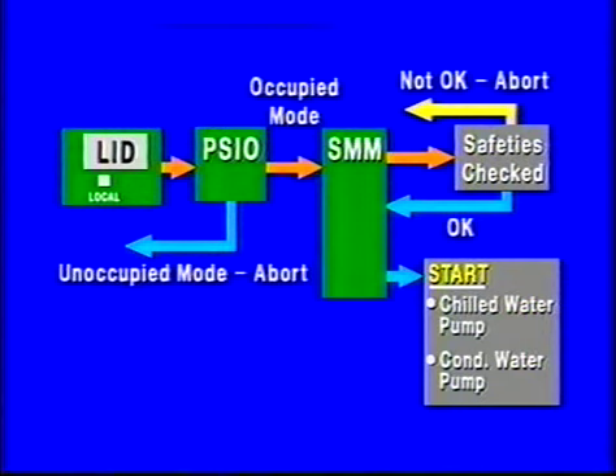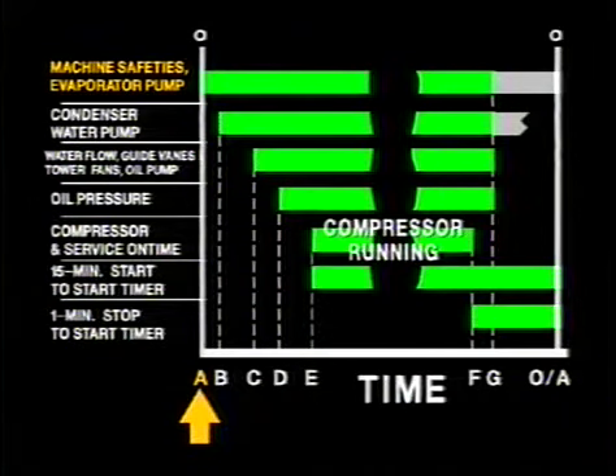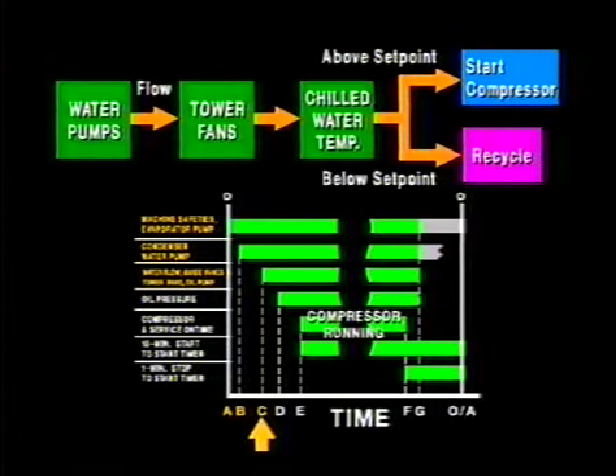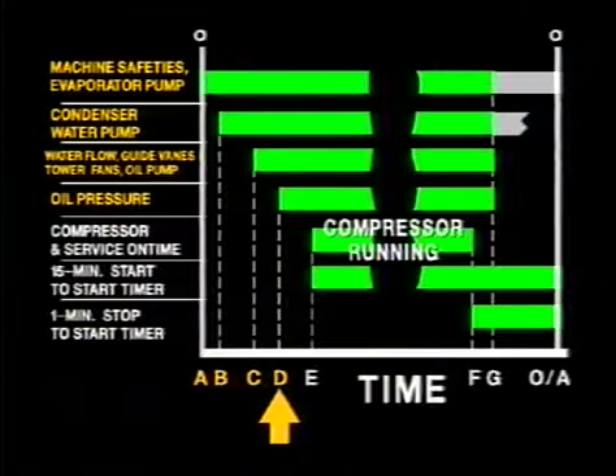Once the local key is depressed and an occupied time period exists, the chiller begins a startup sequence, where it first checks to see if there are any alarms or alerts in effect. If there are none, it starts the chilled water pump and condenser water pump, cooling tower fan, and confirms water flow. The chilled water temperature is then compared to the set point to determine if the chilled water needs cooling. The set point is the desired temperature of the chilled water as it circulates through the building, and is normally configured at the time of initial startup and checkout. If the chilled water temperature is above set point, the sequence continues and the compressor guide vanes are checked for closure. If the guide vanes are closed, the oil pump is started and lube oil pressure confirmed.